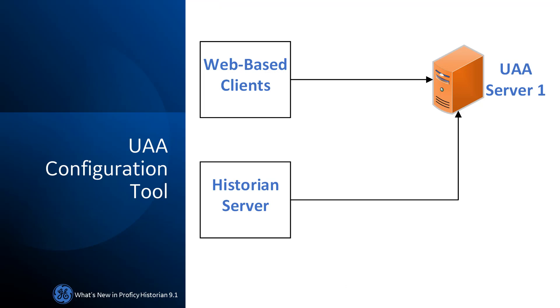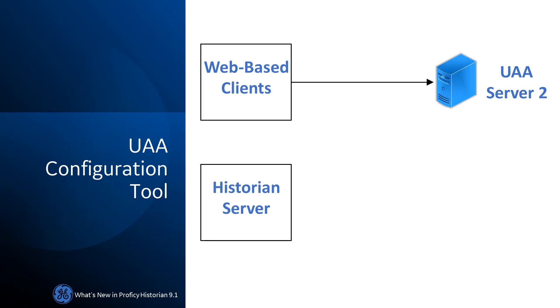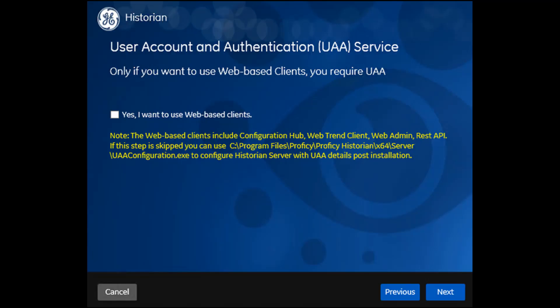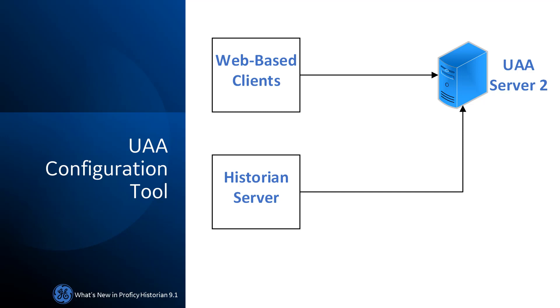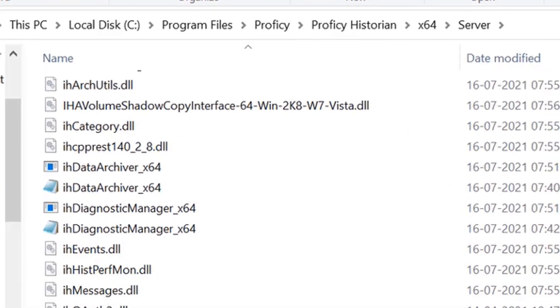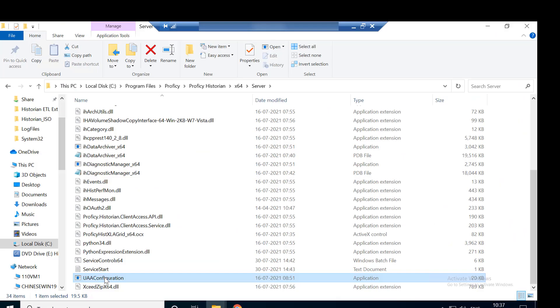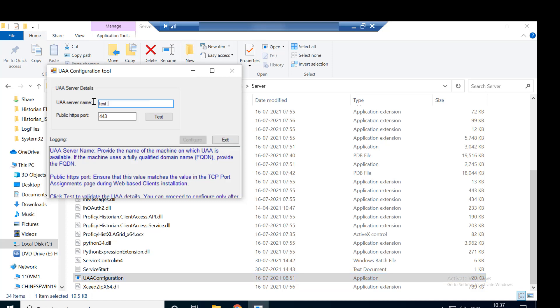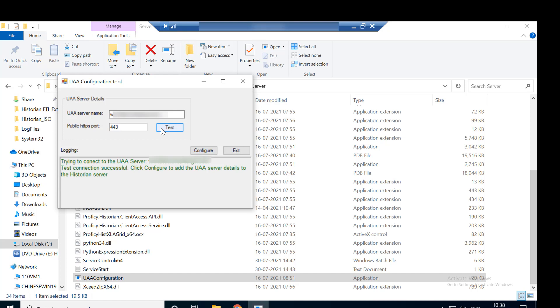UAA Configuration Tool. For you to access web-based clients, the Historian server and web-based clients must always point to the same UAA server. If, however, you have changed the UAA server used by web-based clients, or if you chose not to install web-based clients during Historian server installation but installed them later, you can now update the UAA server details for the Historian server without the need to reinstall it. To facilitate this enhancement, the UAA Configuration Tool has been introduced. Using this tool, you can provide the UAA server details that you provided during the installation of web-based clients.